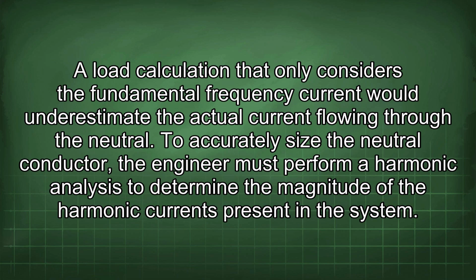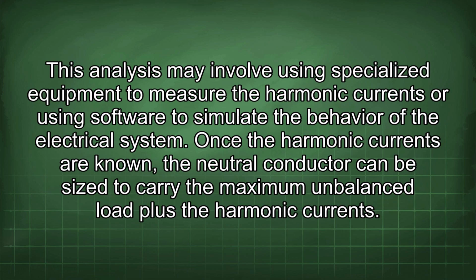To accurately size the neutral conductor, the engineer must perform a harmonic analysis to determine the magnitude of the harmonic currents present in the system. This analysis may involve using specialized equipment to measure the harmonic currents or using software to simulate the behavior of the electrical system. Once the harmonic currents are known, the neutral conductor can be sized to carry the maximum unbalanced load plus the harmonic currents.